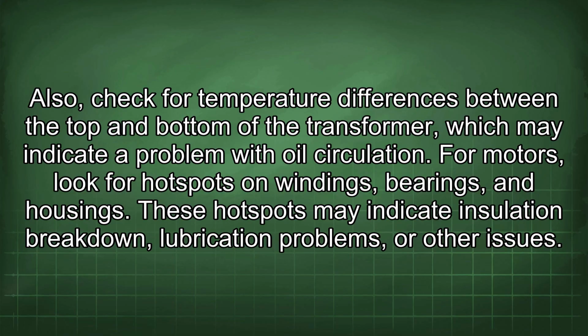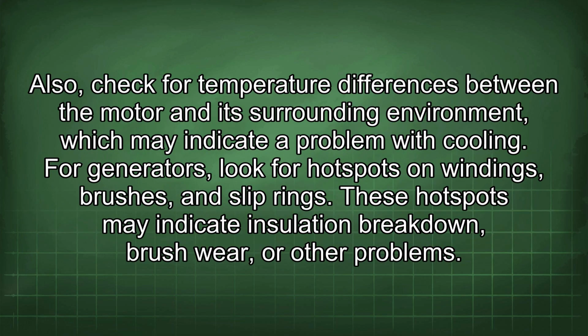For motors, look for hotspots on windings, bearings, and housings. These hotspots may indicate insulation breakdown, lubrication problems, or other issues. Also, check for temperature differences between the motor and its surrounding environment, which may indicate a problem with cooling.